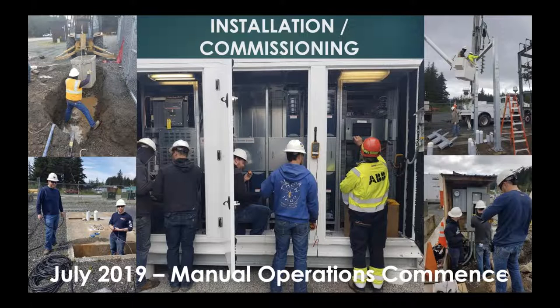Here you can see one ABB staff member and all four CEC employees involved in the commissioning. Our package was purchased as a pre-certified containerized unit, so both the PCS from Hitachi ABB and the SAFT module were rated. They had all the fire systems pre-installed, built and assembled in Florida, and delivered fully compliant for access and so forth. This greatly accelerated our on-the-ground commissioning.